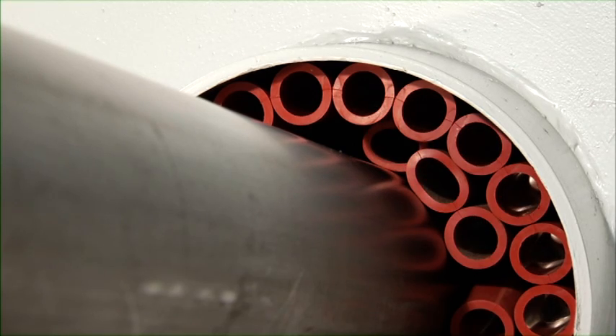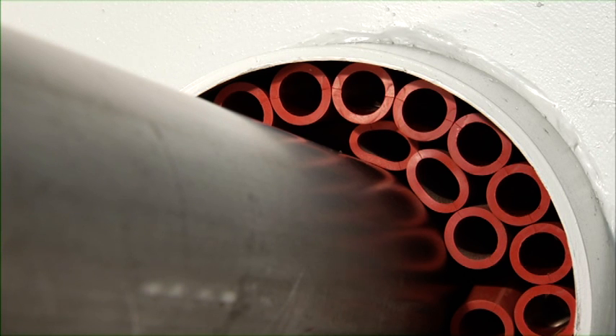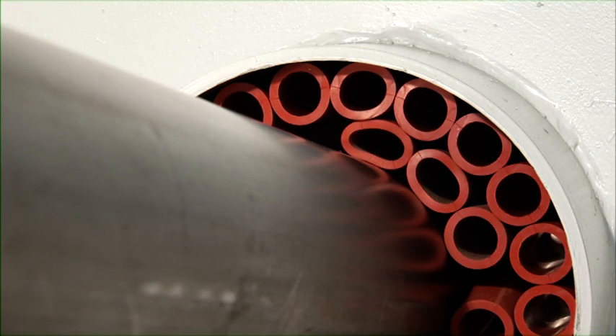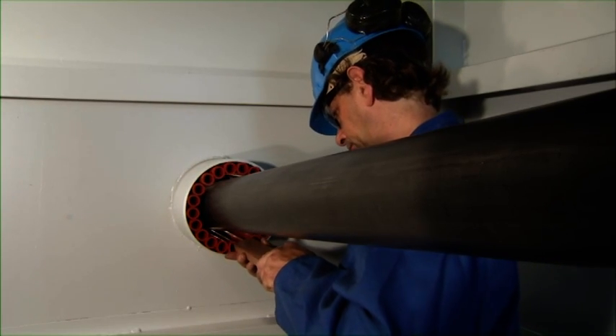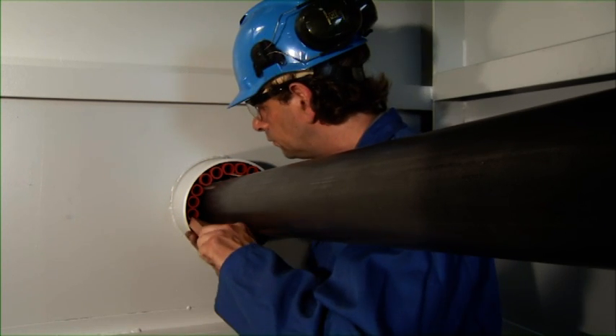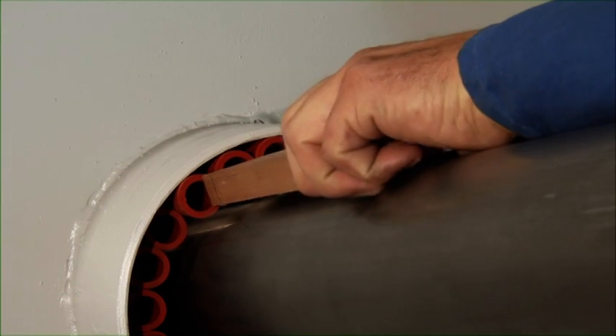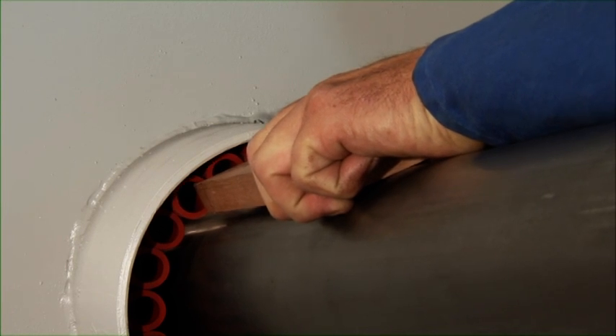After filling up the conduit with filler sleeves, the sleeves are adjusted to ensure they are recessed 20mm into the conduit. For this reason, a piece of wood is used with a distance of 20mm marked on it.